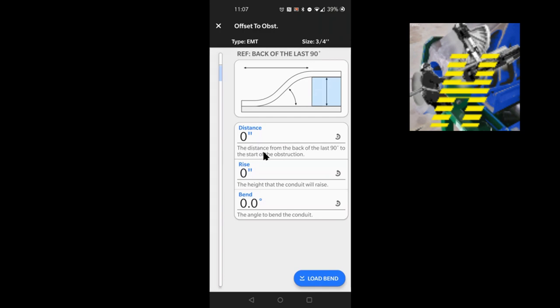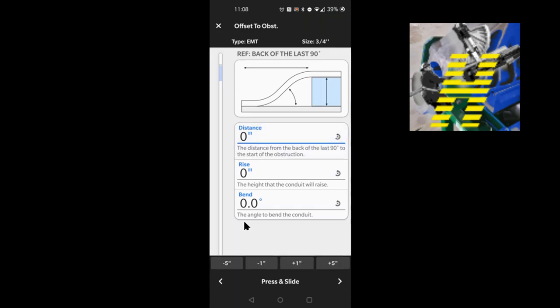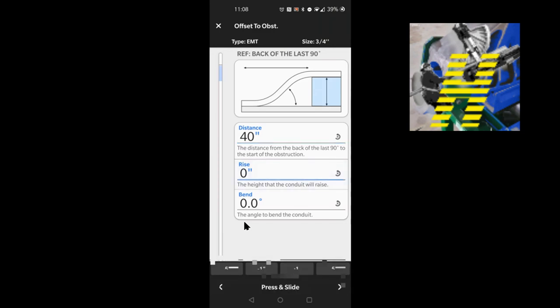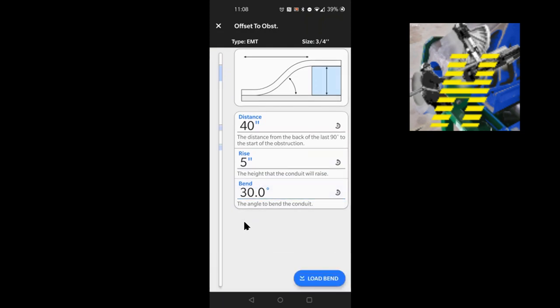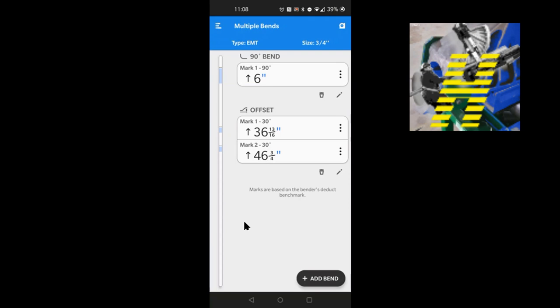We selected the offset and it wants all this information: the distance from the back of the last 90 to the start of the obstruction, the height of the offset — basically the height of the obstruction — and the angle you want to bend this offset at. Let's say the obstruction is 40 inches from the back of the 90, the rise is five inches, and we want 30-degree standard bends. Press Load Bend — it gives you all the layouts for your first and second mark for the offset.